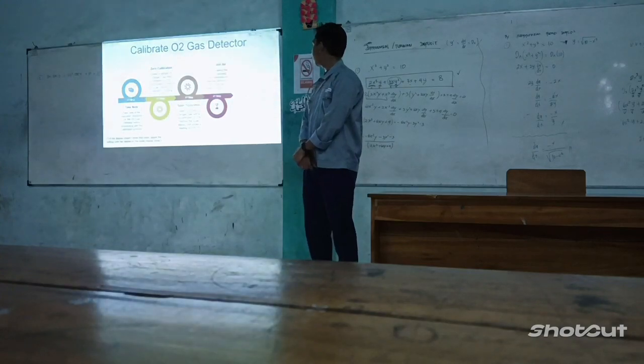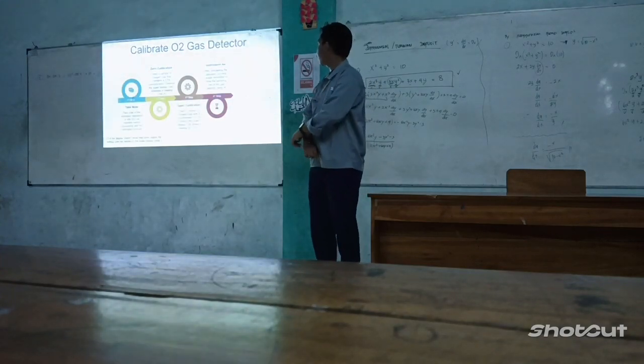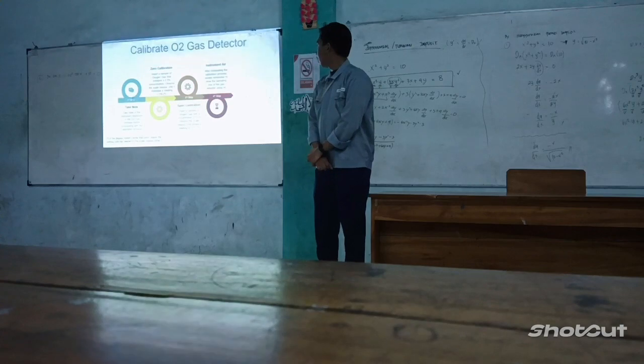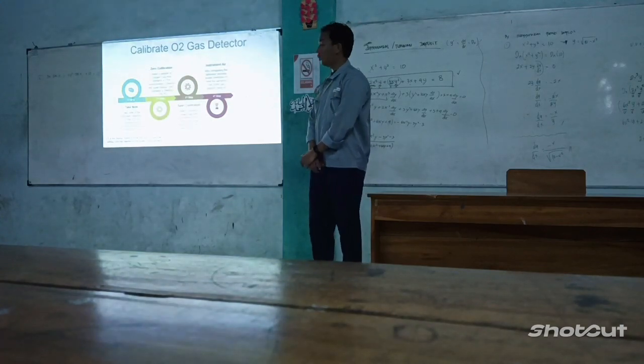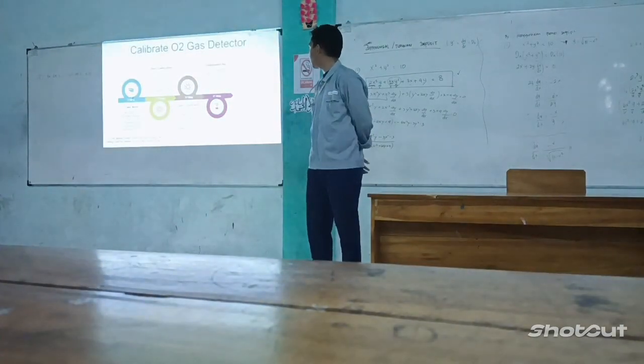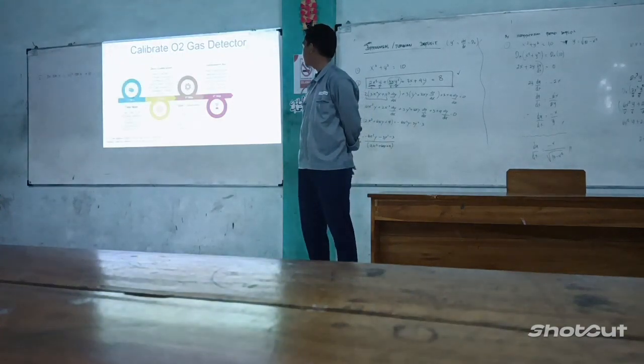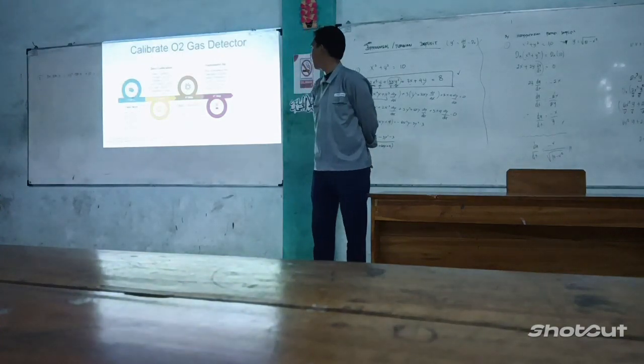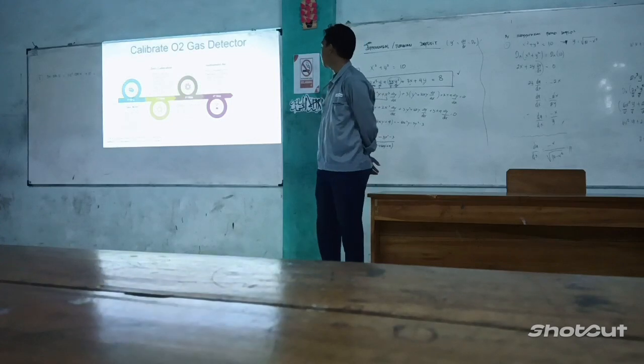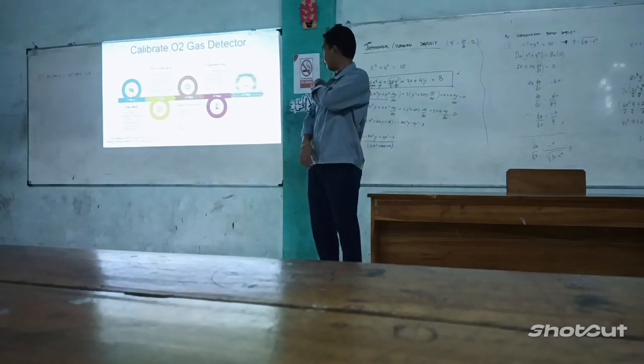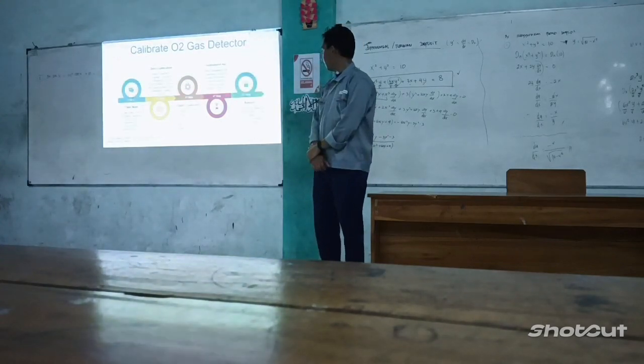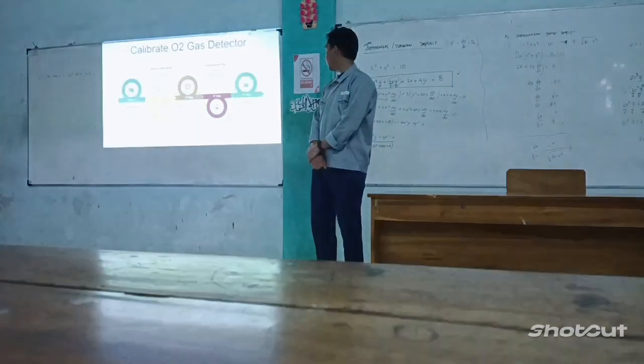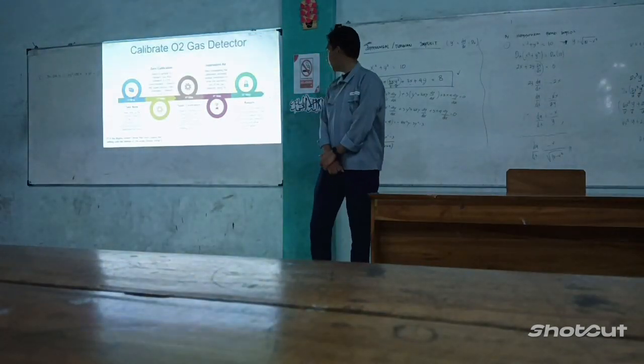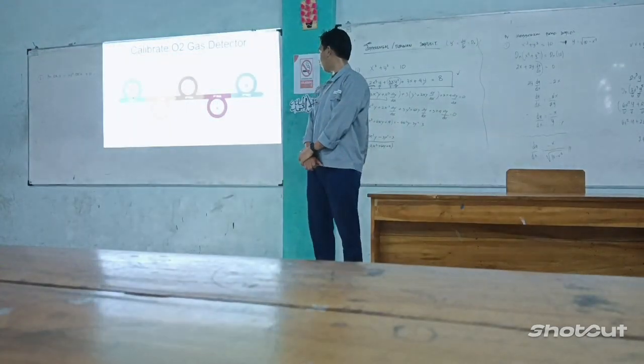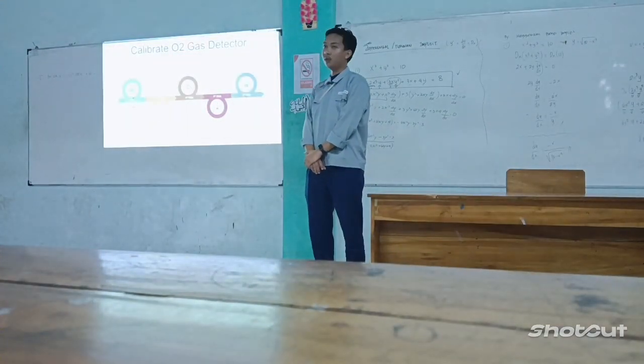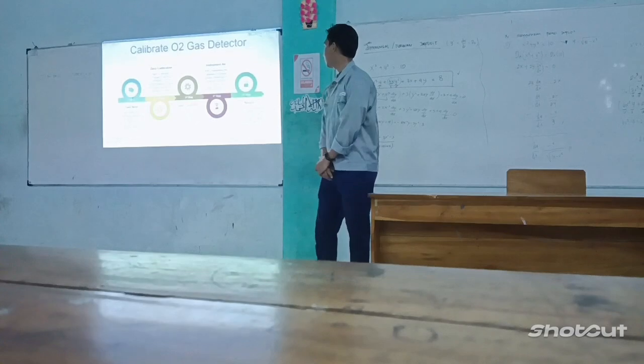The fourth step is instrument air. We do this after completing the calibration process. Please remember to blow the sampling line of the gas detector using instrument air. The fifth step is return. Return the gas detector sampling position to the original position and record the gas detector indication after calibration.